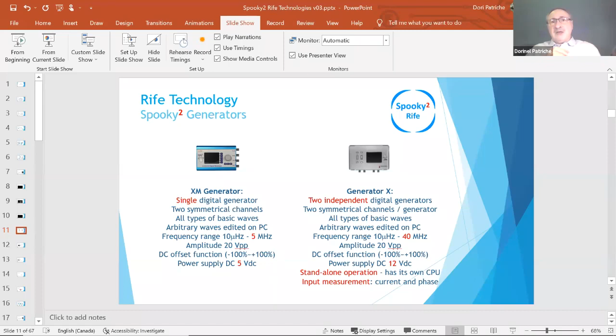Another big difference is that Generator X can measure the current and the phase of the output signal, sensing in this way the reaction of the body to a certain frequency. This trait is useful for a biofeedback scan that can be done very fast, usually under 10 minutes, without the need of any other accessories. The XM generator needs external accessories to monitor the heart rhythm in order to do the scan, which usually takes about 1 hour. A less significant difference is the power adapter, 5 volts versus 12 volts DC. In case you have both types of generator, you must be careful not to mix the power adapters. Finally, the last difference is the price. It's about a 1:5 ratio. So your choice should be based on two factors: budget and type of application.